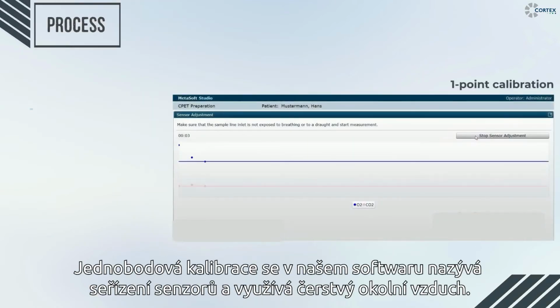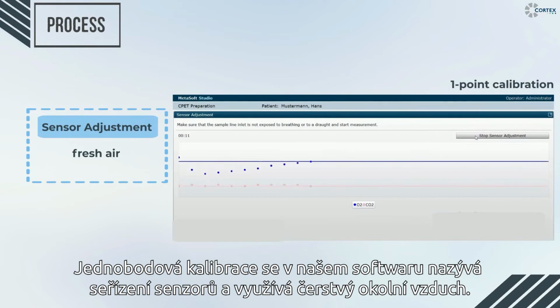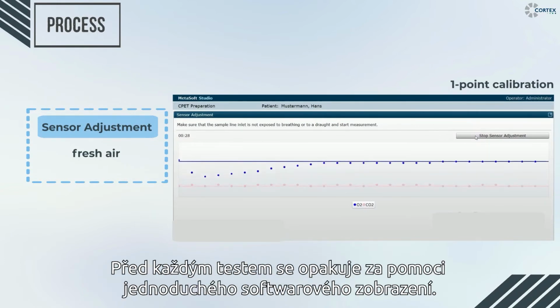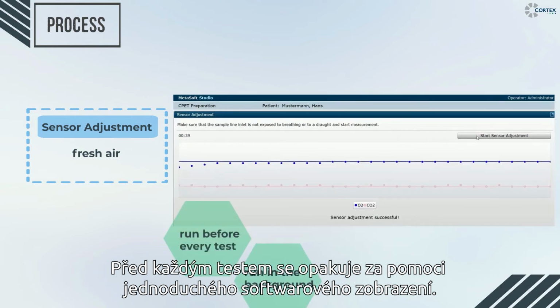The 1 point calibration, in our software, is called sensor adjustment and uses fresh ambient air to perform its validity. As described earlier, this step is repeated before each test with the help of a background view.